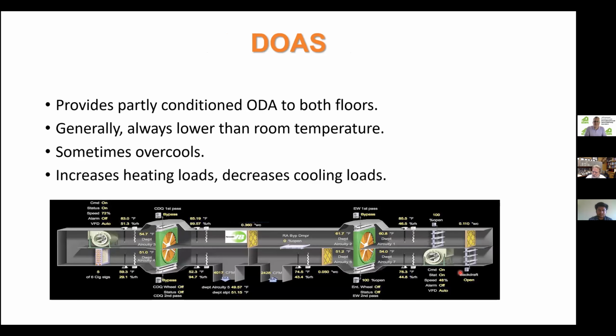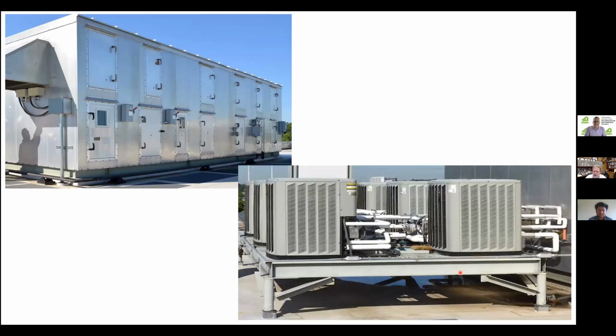So there's also a DOAS system, and it provided, I'd say, partly conditioned outdoor air to both floors. It was generally always lower than the room temperature. So in the summer, the DOAS system would actively be cooling. And in the winter, it wouldn't actively heat, but be recovering heat. So the outdoor air was warm some, but not up to room temperature. So generally speaking, the DOAS increased the heating loads for the other two systems and decreased their cooling loads. This is the DOAS system with what looks to me like a bunch of residential units piped into the air handler portion here.